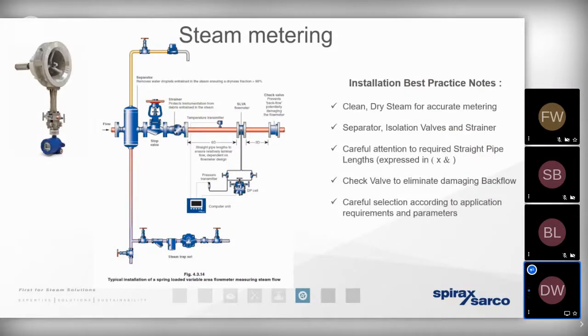But it's still good working practice to fit a steam meter. Just for good working practice purposes, we want to ensure that we've got a steam meter fitted ahead of the process and in the boiler house. So that could be for budgetary purposes, it could be so we're monitoring any distribution losses between the boiler house and the process, or it could be for fault finding.